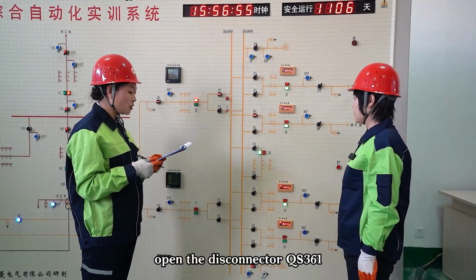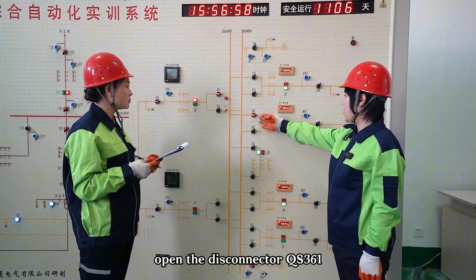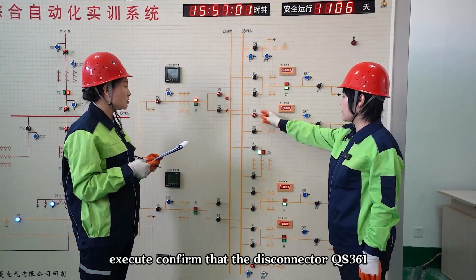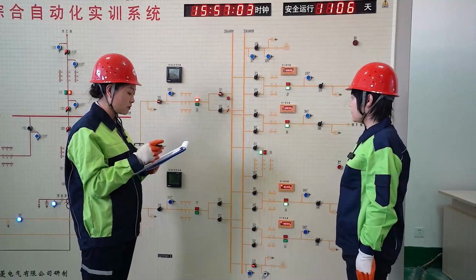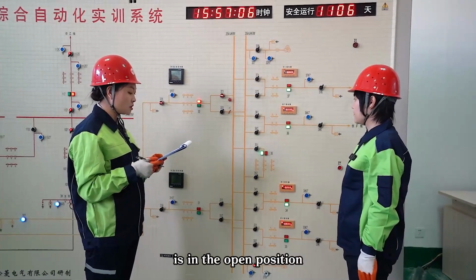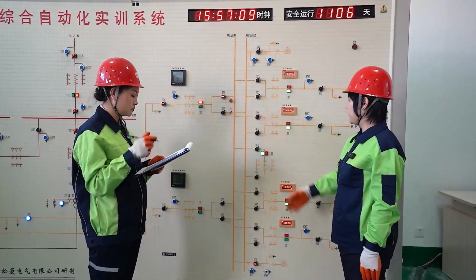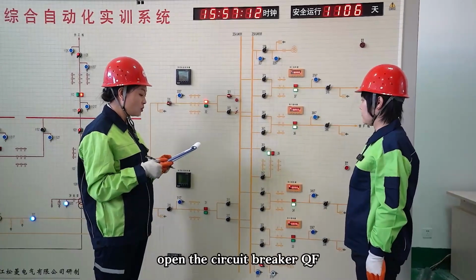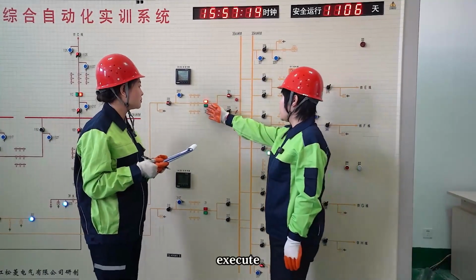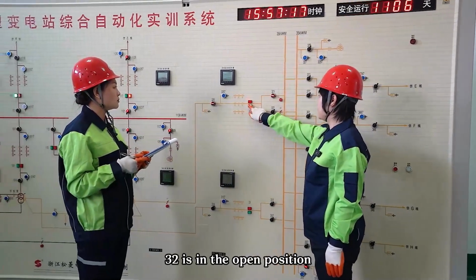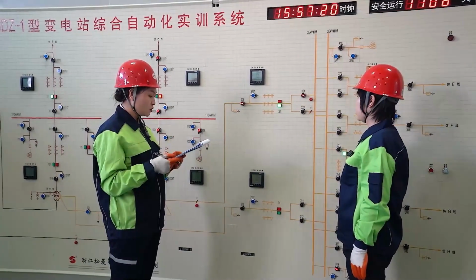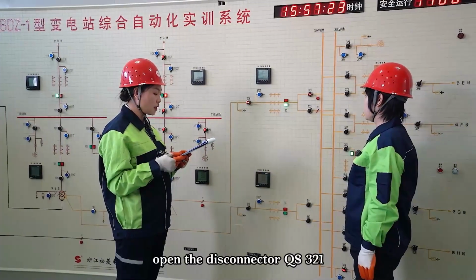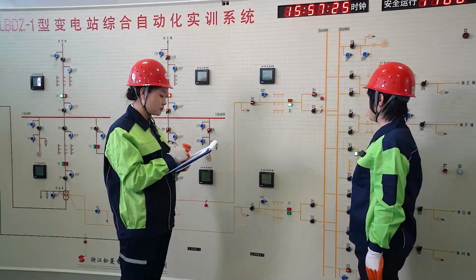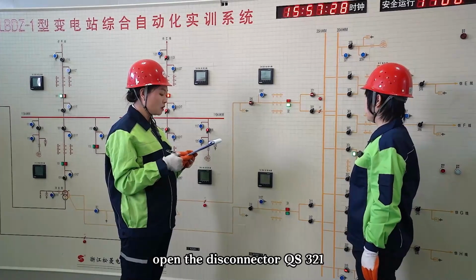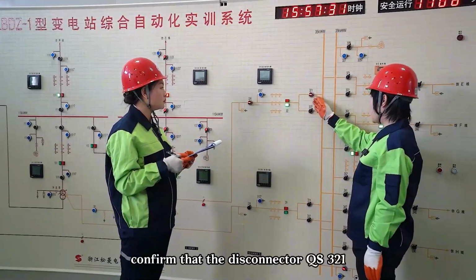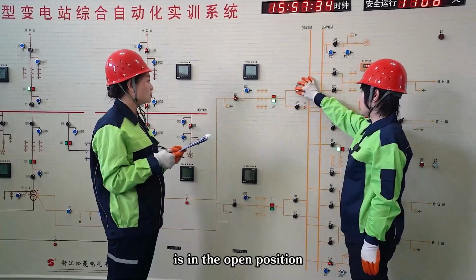Open the disconnector QS361. Execute. Confirm that the disconnector QS361 is in the open position. Confirmed. Open the circuit breaker QF32. Execute. Confirm that the circuit breaker QF32 is in the open position. Confirmed. Open the disconnector QS321. Execute. Confirm that the disconnector QS321 is in the open position.